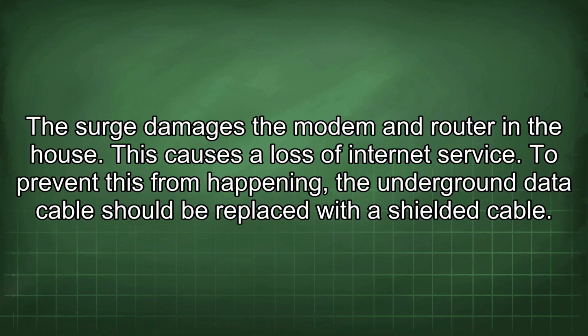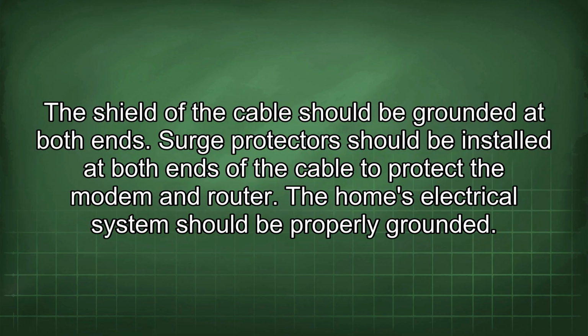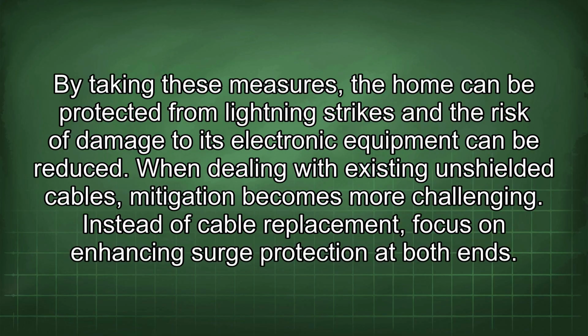To prevent this from happening, the underground data cable should be replaced with a shielded cable. The shield of the cable should be grounded at both ends. Surge protectors should be installed at both ends of the cable to protect the modem and router. The home's electrical system should be properly grounded. By taking these measures, the home can be protected from lightning strikes and the risk of damage to its electronic equipment can be reduced. When dealing with existing unshielded cables, mitigation becomes more challenging.